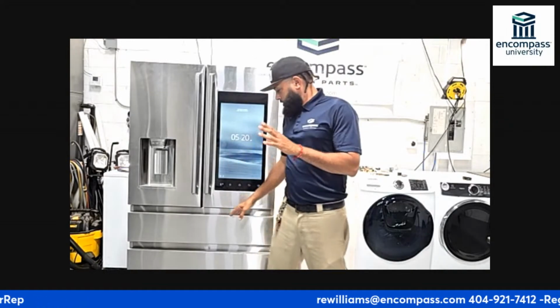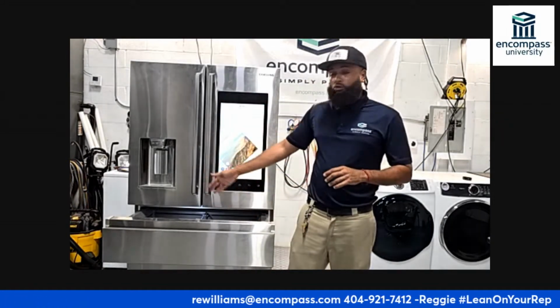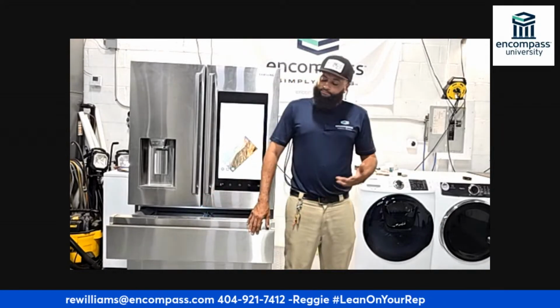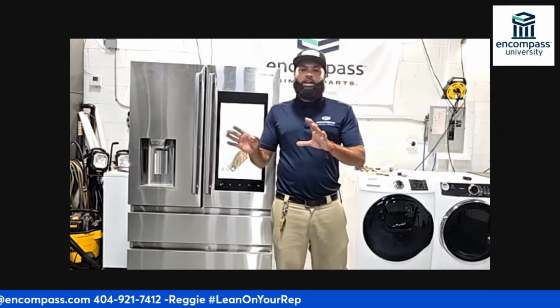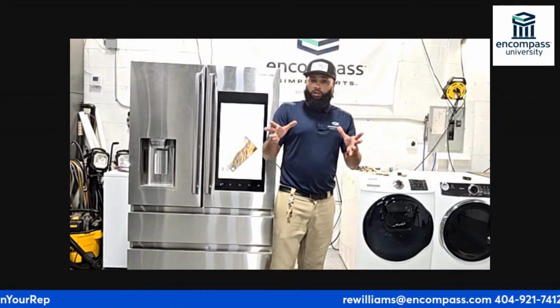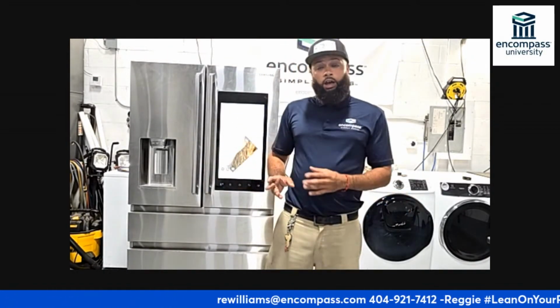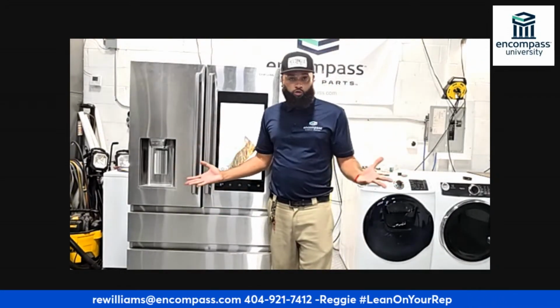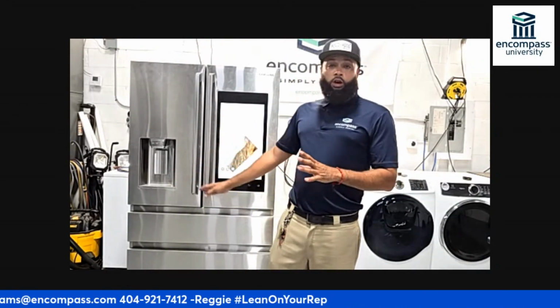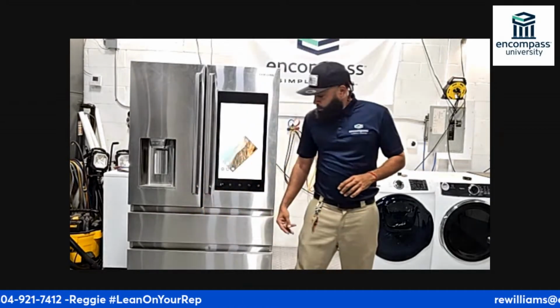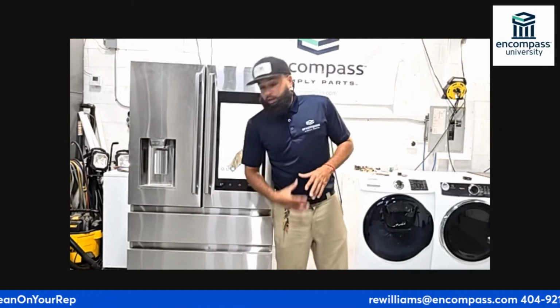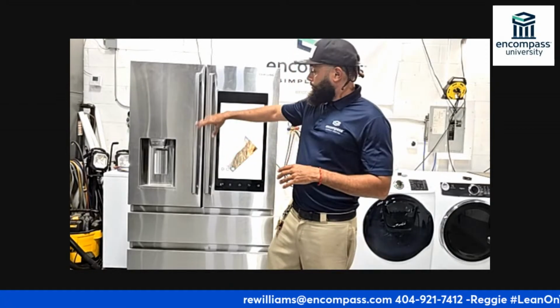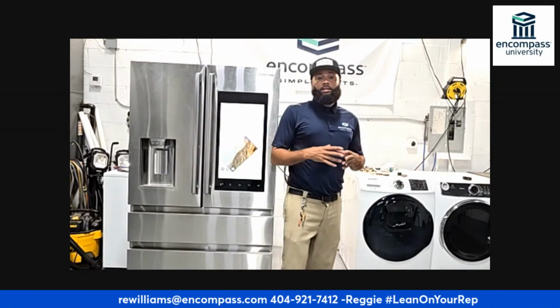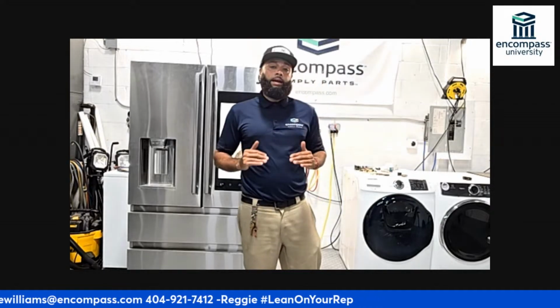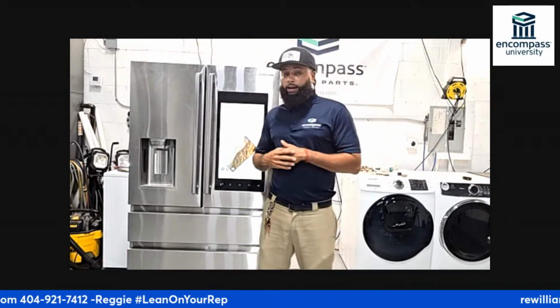Now in certain units you'll get a third zone called the flex zone. You can monitor that according to the items you place into it — some manufacturers make it for wine bottles, some for produce or vegetation, whatever you want to do. But more importantly, freezer you want 0 plus or minus 3, fresh food 37 plus or minus 3. Those are the target temps this box needs to operate correctly.